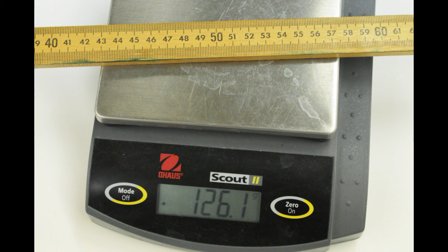Two force sensors will be used and must both be calibrated. Calibrate them in the upward position, placing a 500-gram weight on top. After calibrating the first sensor, go to the top of the calibration window and select the second force sensor, repeating the calibration procedure for it.